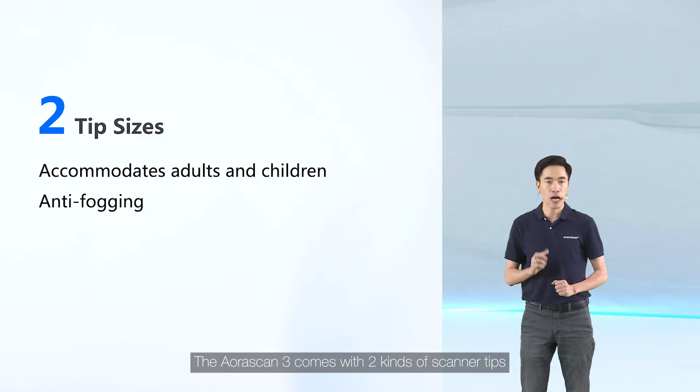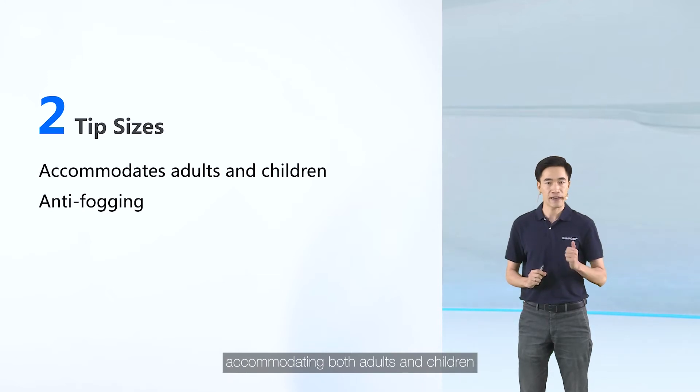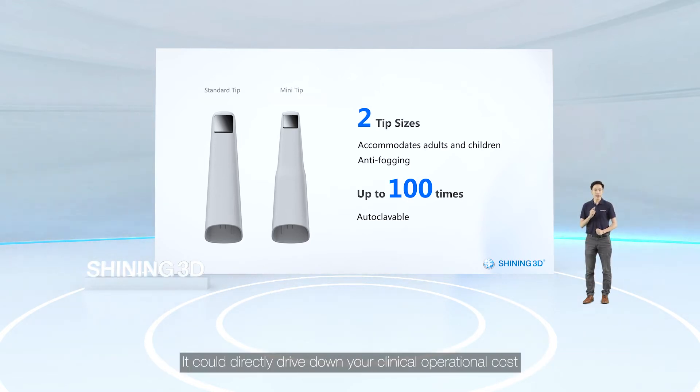The Aorascan 3 comes with two kinds of scanner tips — standard size and mini size — accommodating both adults and children. The coated mirror is equipped with an anti-fogging function, and these scanner tips can withstand up to 100 times of autoclave sterilization, which can directly drive down your clinical operational cost.